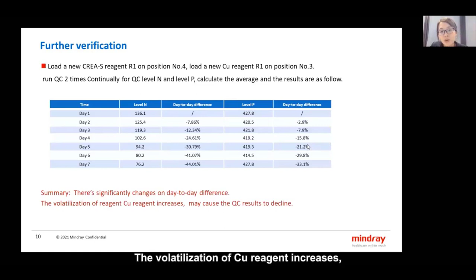We can look at another further verification. Then we loaded a new creatinine reagent R1 on position number 4, and loaded a new Cu reagent R1 on position number 3, and ran QC 2 times continuously for QC level N and level P, calculated the average, and the test results are as follows. As you can see, there is a significant change in day-to-day differences, and the volatilization of the Cu reagent may cause the QC result to decline.